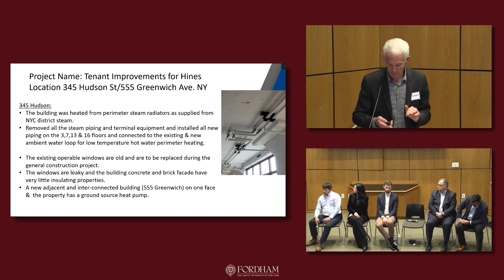The interesting thing about the 345 Hudson site is it's got German-based multi-pass fin tube radiators rated for 100-degree Fahrenheit supply water temperature with a 20-degree delta T, acting as basically terminal baseboards for convection heat under the windows per floor. We're actively watching how well this is going to work. It's, again, very low-grade heat, if you will, in terms of a water source to replace steam radiators that would be giving out 220 degrees. But you can see the width of the fin tube there and how wide it is to get the surface area to get the convective heat that you need. It's like 4 times the transfer rate compared to a traditional single-pass type system.